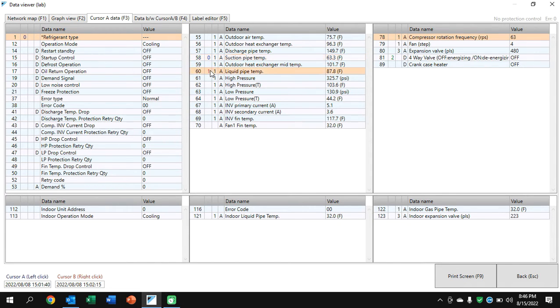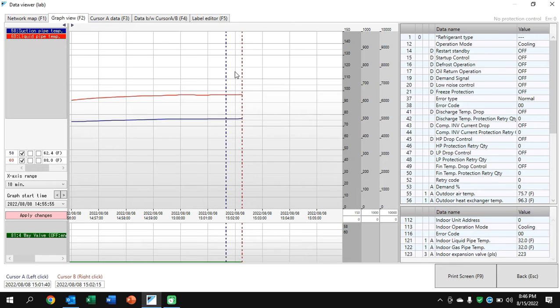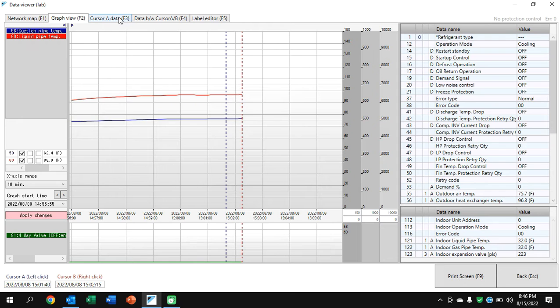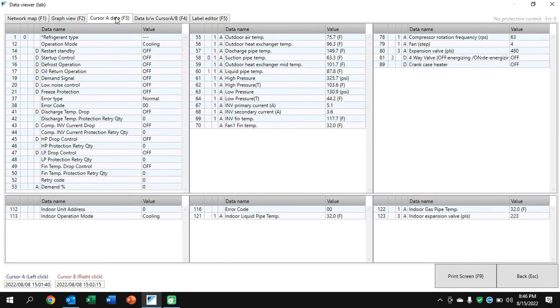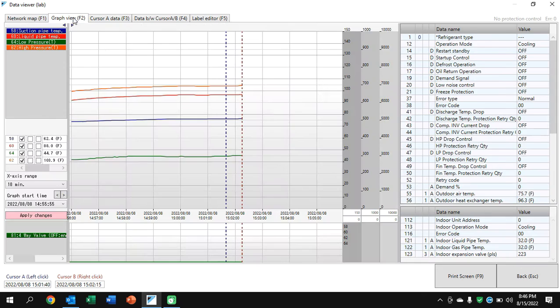I'm not super concerned with the one I have there on digital that will be on the lower part of the screen. I'm going to leave that on so we can see what's going on there. I'm going to go ahead and choose my suction and my liquid. And if I look down, I'll also see my pressures located on there. And if you can see these two located here, and we've got our temperatures there on the left, we'll see where they're at. But I want to actually look at my superheat and subcool. So I will see my pressures on the right-hand side of the cursor data, but I'll also see the pressure with a T. And that T in parentheses is for the temperature saturated. So I'll click on the low and the high both, and this is going to give us the saturation right off the chart.